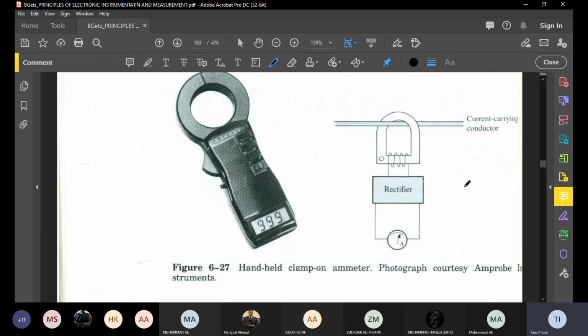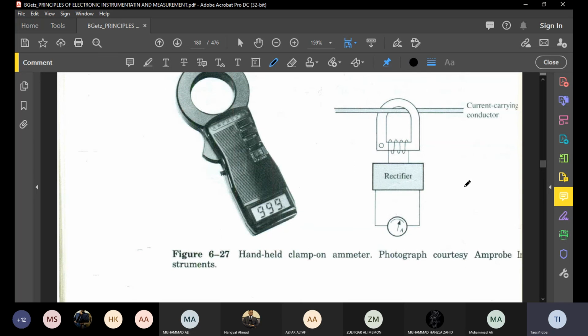So this core has a secondary winding, and therefore the current carrying conductor will produce a magnetic field, and the core is going to detect that magnetic field, and ultimately the secondary coil is going to get some voltage due to that magnetic field. And basically this magnetic field is going to be sinusoidal, for example, so we need a rectifier to get the DC value in the meter.